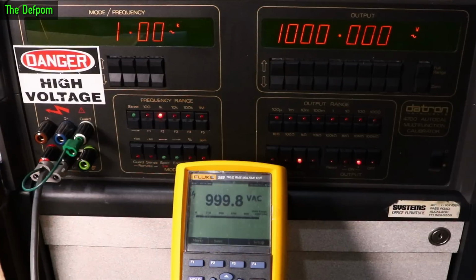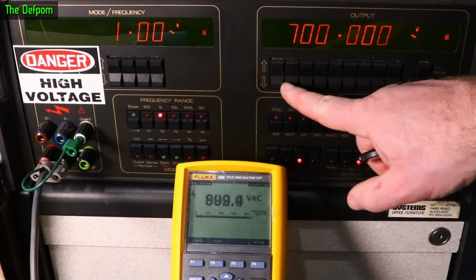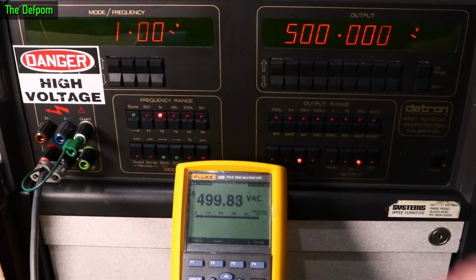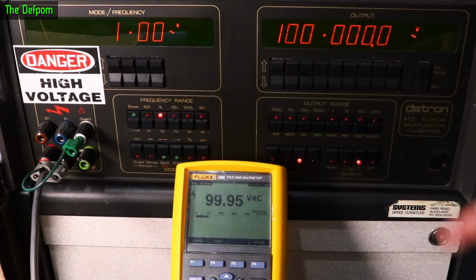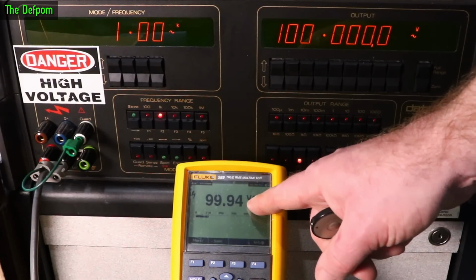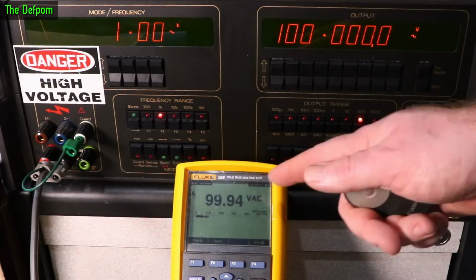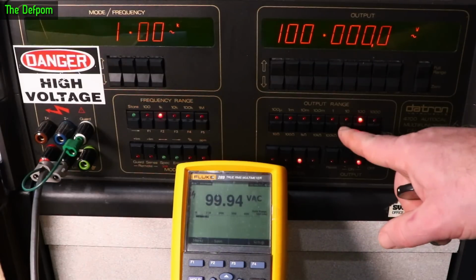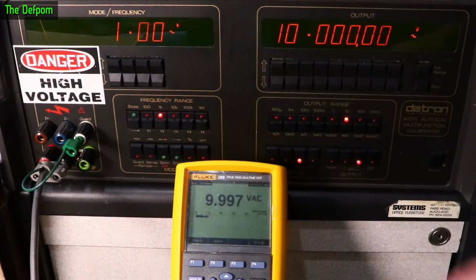Let's change frequencies. So I've changed frequencies to 1 kilohertz now. And we're now reading slightly low instead. So I go down to say 500 again. So I'm going to go 400 then 500. So it goes to the top of that scale. And that's reading down a little bit. And 50 volts. Yep. Let's do 100 volts there. So 100 volts settled down to be sort of 4 or 5 counts, sort of 6 counts, 7 counts maybe below. Okay, so 10 volts is a few counts down.